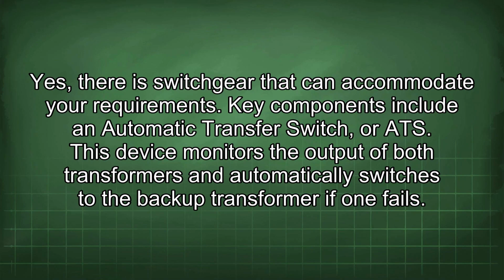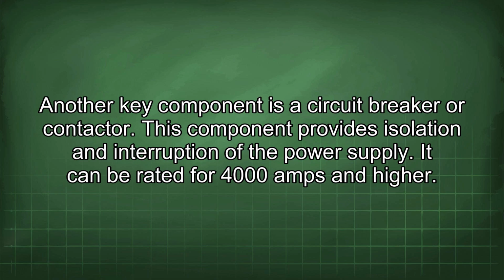Yes, there is switchgear that can accommodate your requirements. Key components include an automatic transfer switch, or ATS. This device monitors the output of both transformers and automatically switches to the backup transformer if one fails. Another key component is a circuit breaker or contactor. This component provides isolation and interruption of the power supply. It can be rated for 4000 amps and higher.